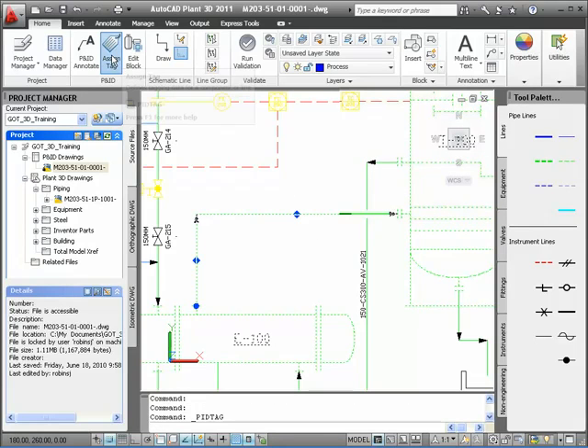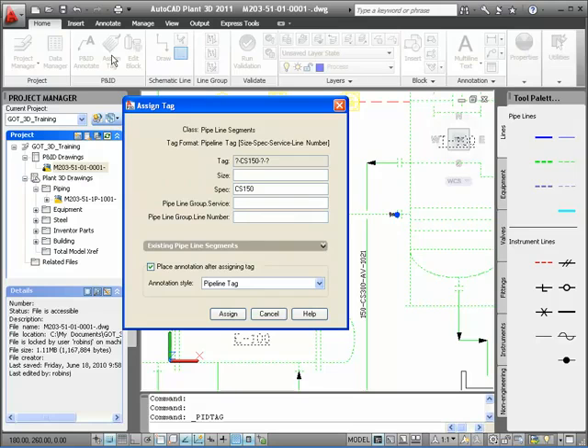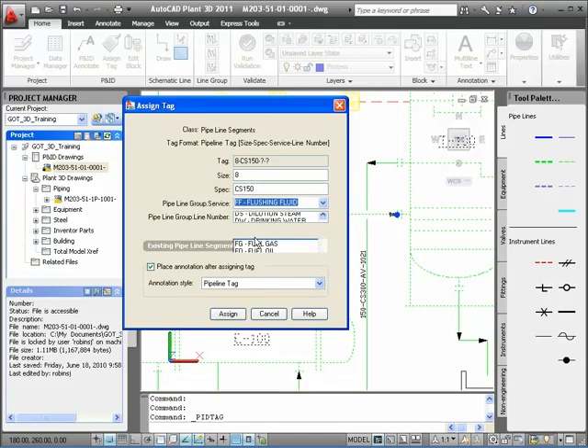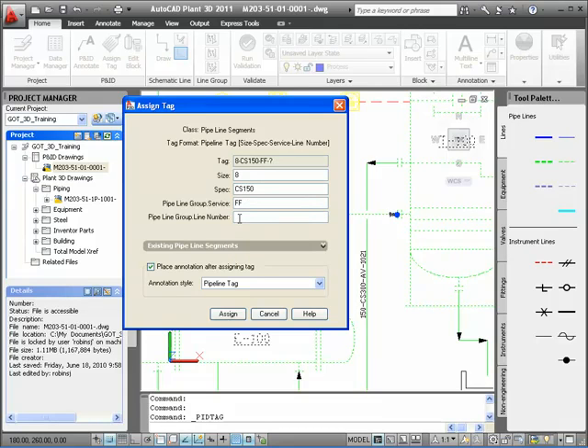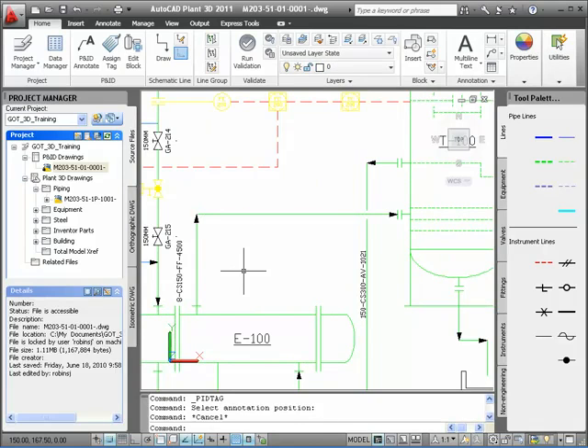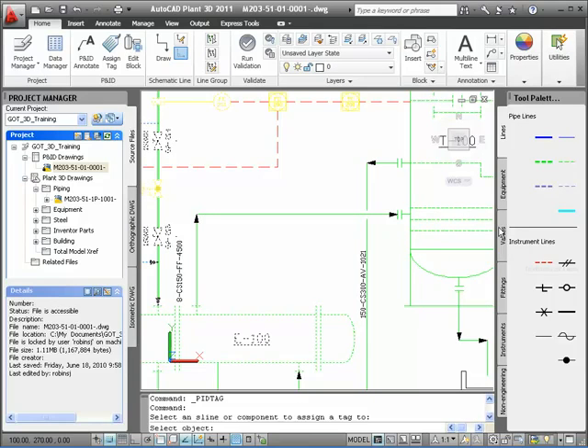I'll then select the line I just created and click the Assign Tag button in the ribbon. In the dialog, I select a size of 8. I'm going to leave the CS150 spec, add service, and finally I'll enter a line number of 4500. The Place Annotation checkbox is checked, so I'll click OK and place my line number annotation.